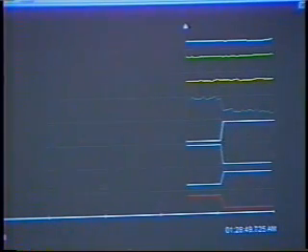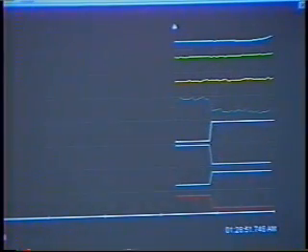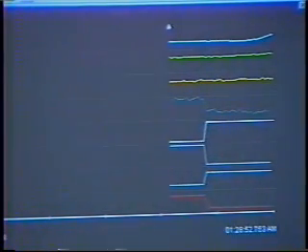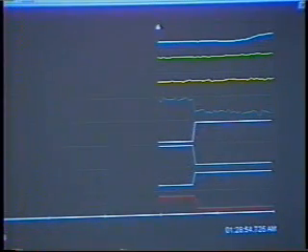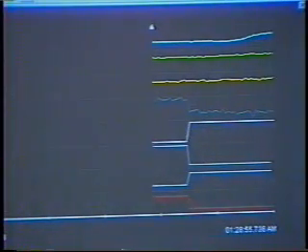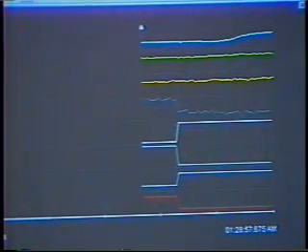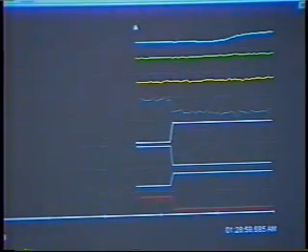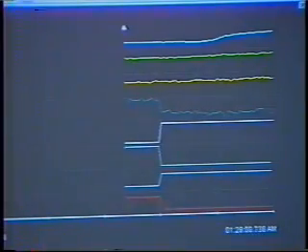As you can see, there was a temperature rise in the transformer as the load varied, but it was well within specifications. Similarly, output regulation was good under all load and line voltage conditions.